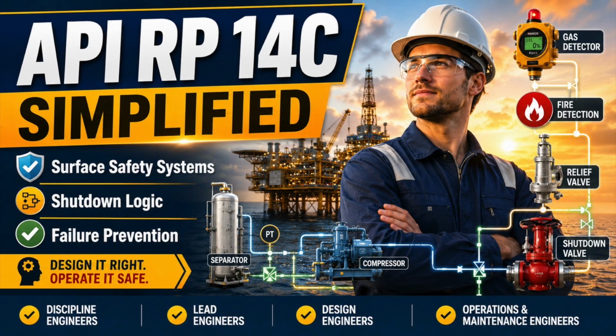Leak protection also requires several detection layers because one device cannot detect every release. A large leak may cause a measurable pressure drop. A small gas leak may continue without changing process pressure but accumulate inside an enclosure.